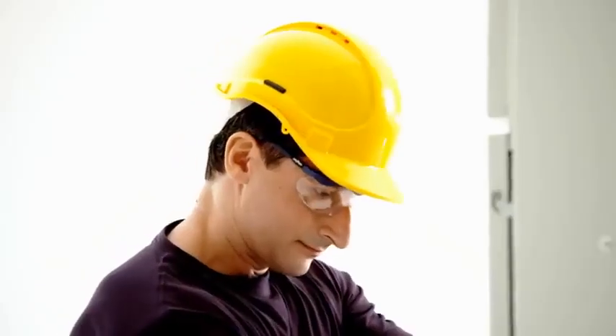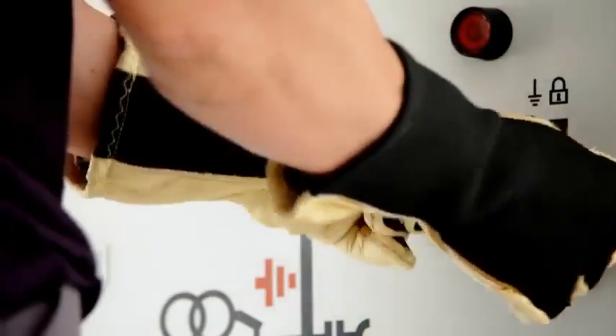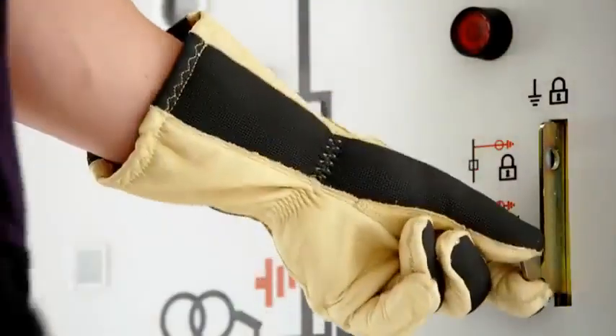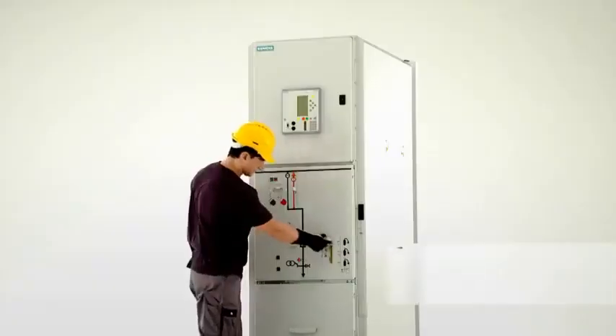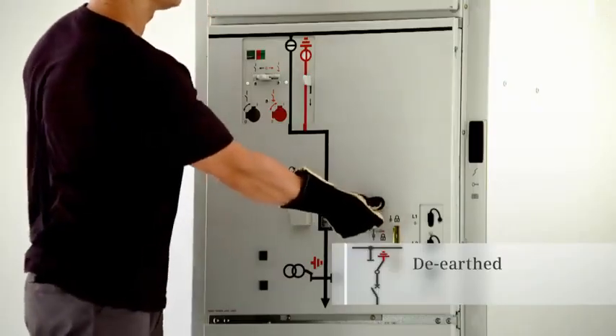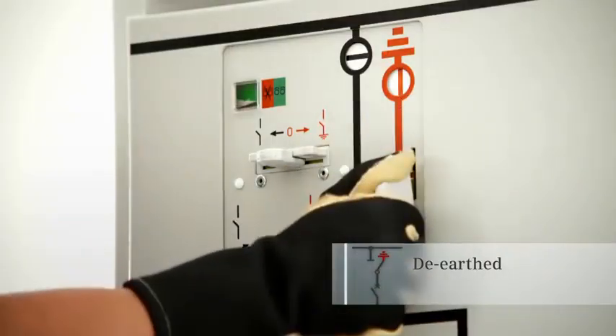To de-earth this feeder the padlock must first be removed rendering the locking device inoperative. The circuit breaker can then be switched to the open position and hence the feeder can be de-earthed.